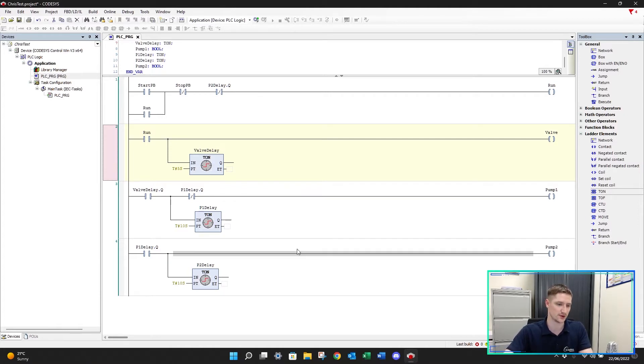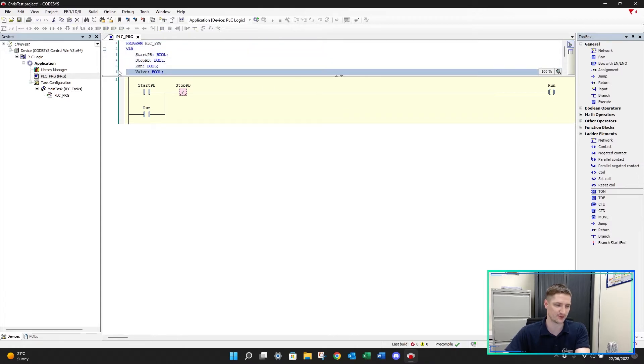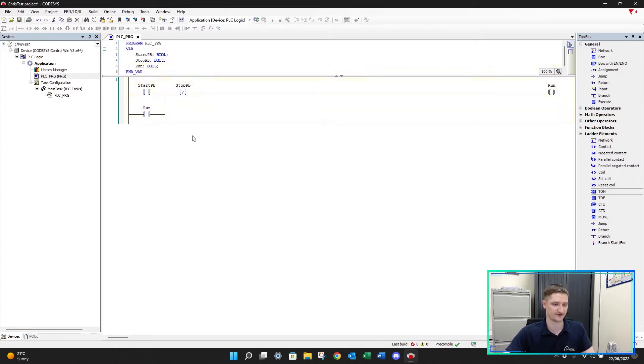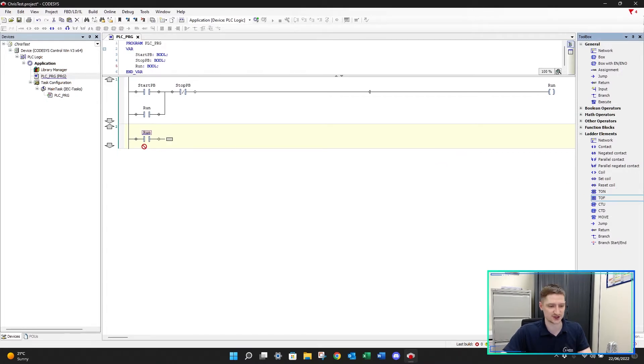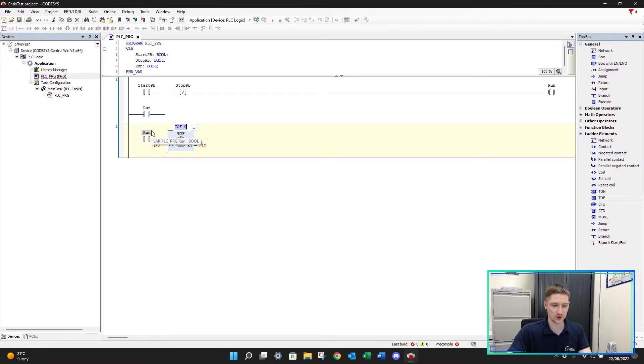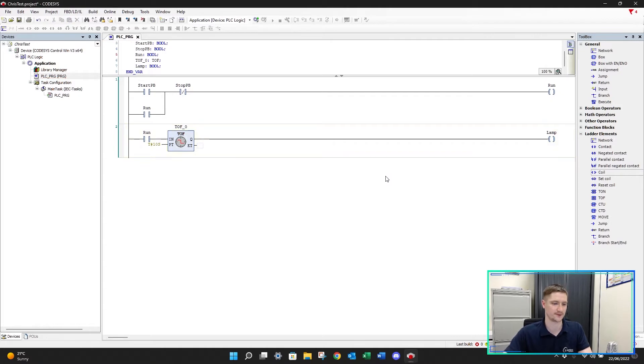Currently we have our program for our valve and pump. I'm going to get rid of this and just show you how the off delay timer works. I'll delete these variables as well, except for our start, stop, and run signal. Let's insert a new network, put in a normally open contact assigned to our run signal, and take that to our TOF timer. We'll leave it as TOF zero, set this to T# 10 seconds, and put an output coil after the TOF tied to a lamp.